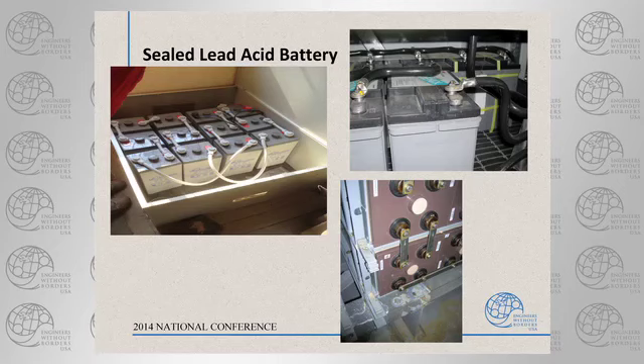So these are some big sealed lead acid. They look like standard 12-volt batteries. This is a 24-volt start system for a diesel engine. But these are labeled maintenance-free, sealed. So there's no vent ports that you can get to. What happens if those leak? Pardon? What happens if they leak? When they leak, as he said, the electrolyte level goes down and it is irreplaceable on most of these. Eventually you're going to have to trash it. You've lost capacity because you've got less acid. You're going to have plates that sulfate, crystallize, and lower the available surface area. So you're losing amp hour capacity.